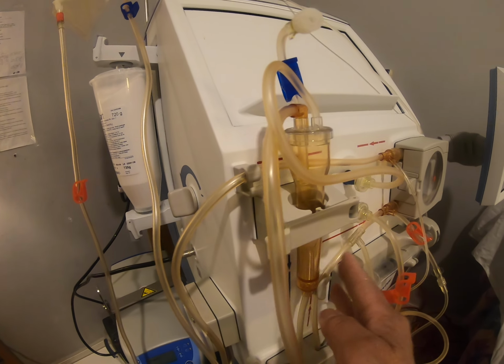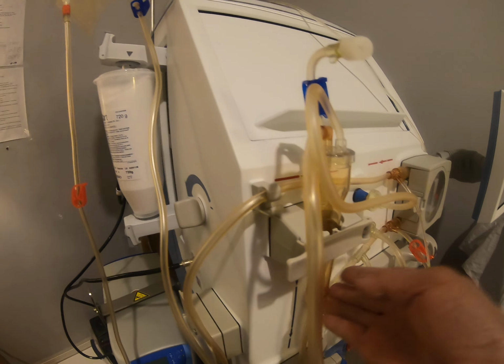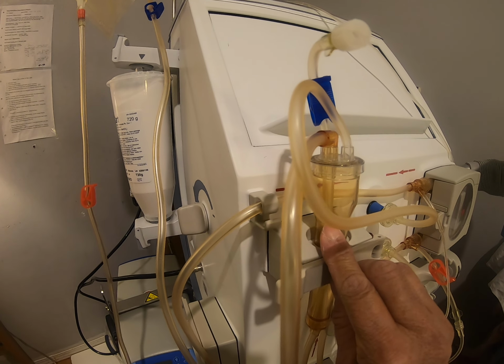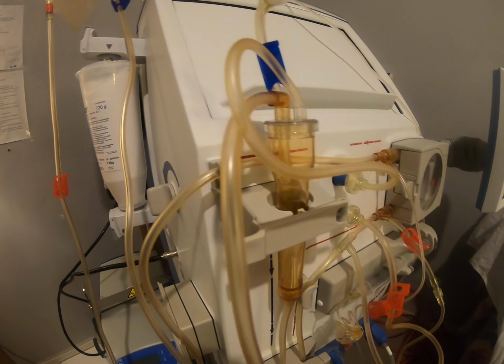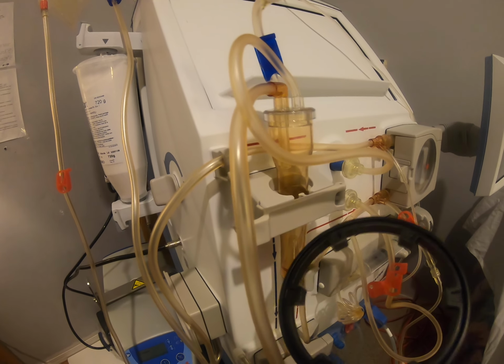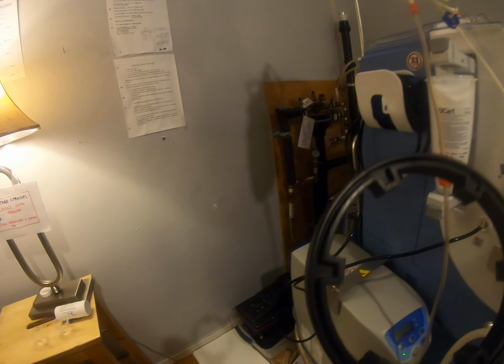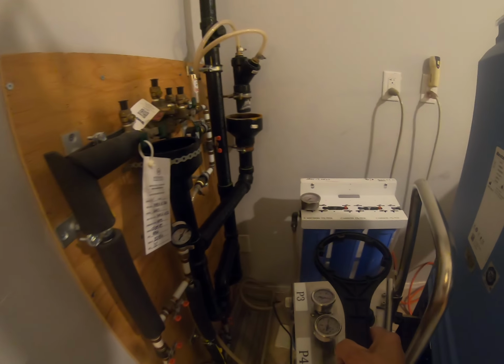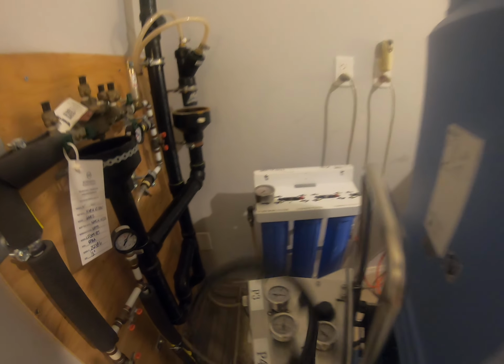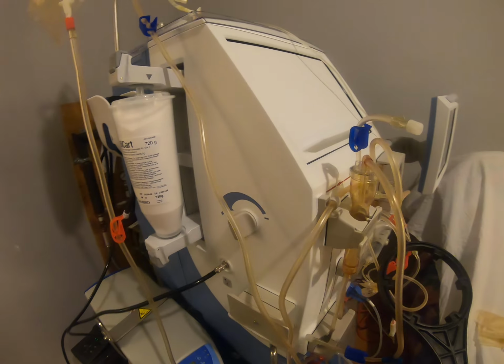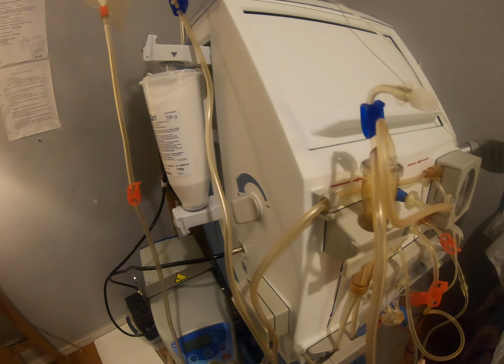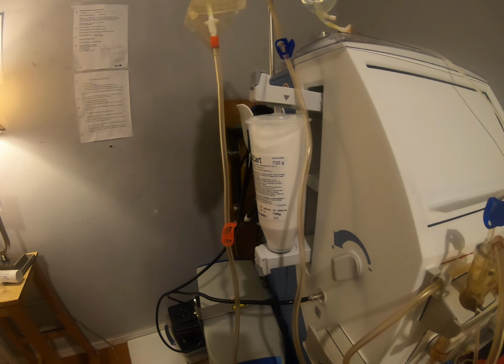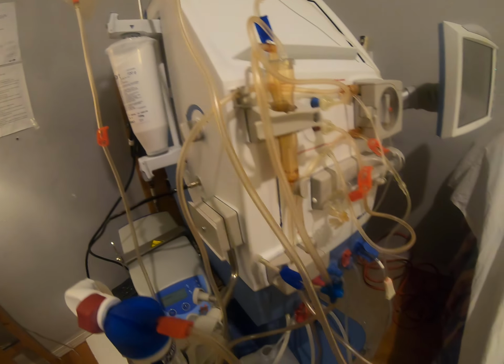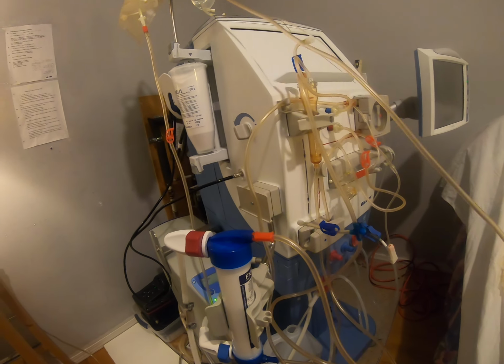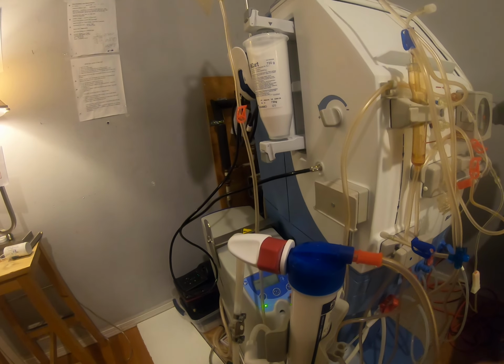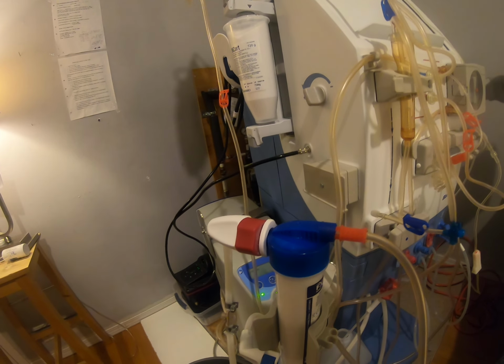So then, when the machine starts going and fills up in the priming phase, this will fill up with fluid. Be sure that the fluid is in good contact with this little tube in here, and then tap it with this one here to remove all the air. This is also used for removing water filters, but it also has the purpose of tapping the air during setting up for dialysis. Then there is another tube. So you trace the end of this tube in here, this venous.